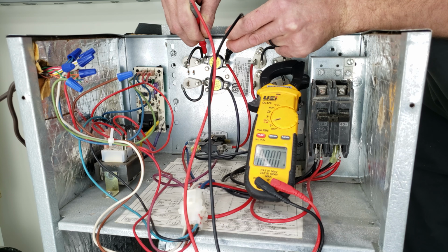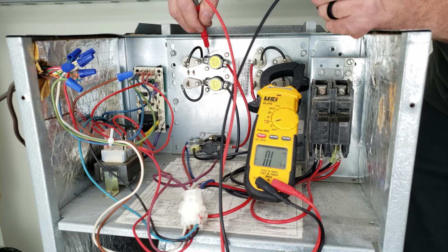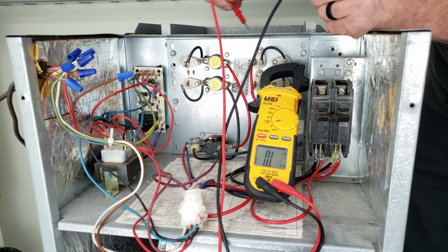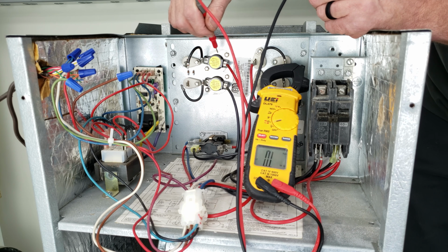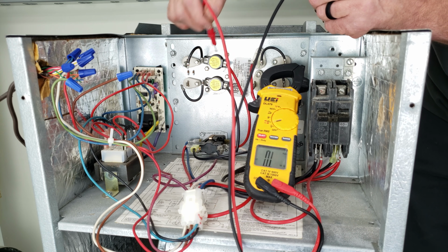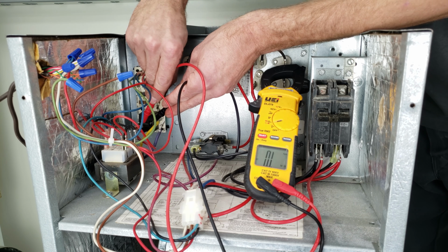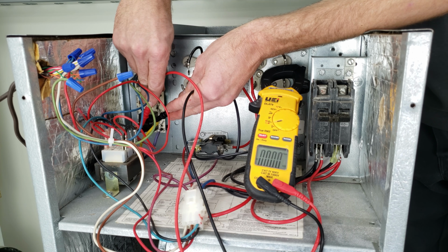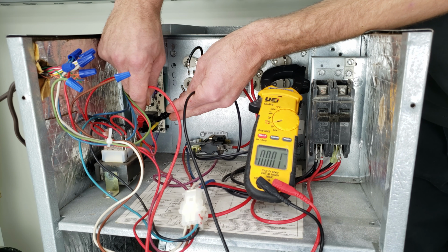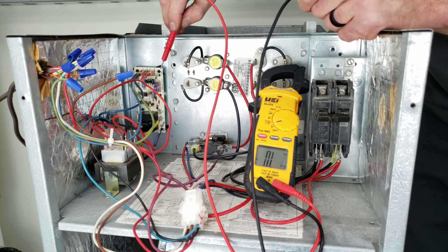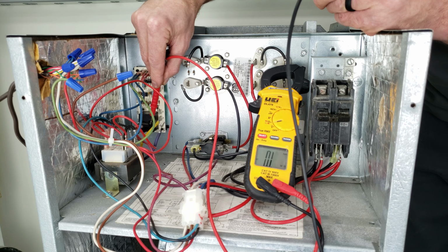So if you had 1 ohm of electrical resistance, that would mean that your voltage is going to drop across here while it's drawing electrical current, while the electric strip heater is running, and that could be an indication of a bad electrical contact. Likewise over here, right now we should have very close to 0.0 ohms across the contacts, the normally closed contacts, but then what's going to happen is when the air handler is running, the contacts between here and here should be closed.